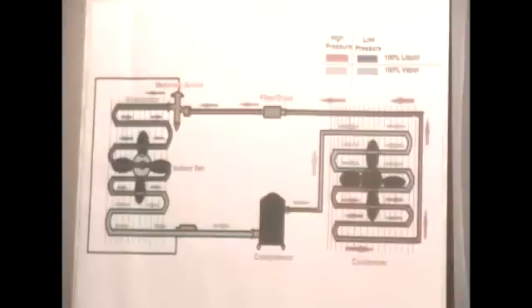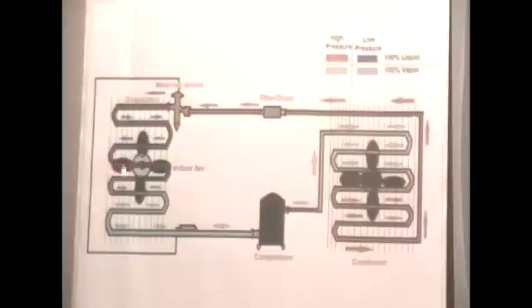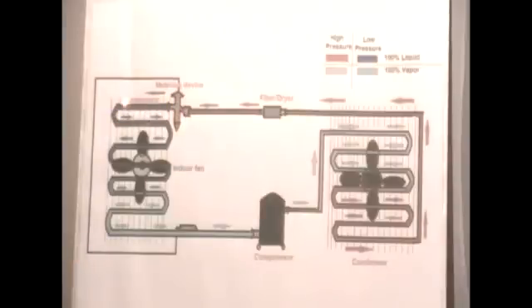From the condenser it goes to your metering device, whose job is to meter how much refrigerant is allowed to go into your evaporator coil. At that point the state is going to be low pressure, 100% liquid. It then absorbs heat from the indoor air passing through the evaporator coil via the indoor fan motor, and it changes the state from low pressure 100% liquid to low pressure 100% vapor, and it goes back to your compressor again. And the cycle begins.